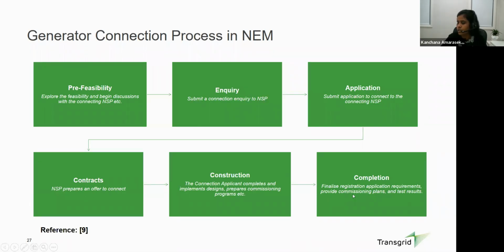During the connection application stage, these plants usually don't have a detailed design, and the models are usually high level. When it comes to the construction stage, they have the detailed design and the detailed models. During the registration, we check whether this final detailed design of the plant can meet the GPS agreed during the connection application stage. And then AEMO grants the approval for registration as a generator. And only then can they start commissioning.